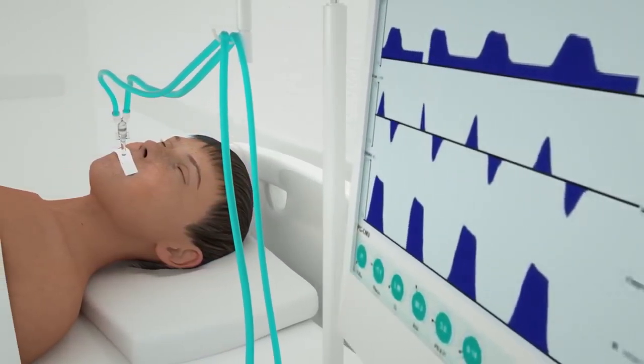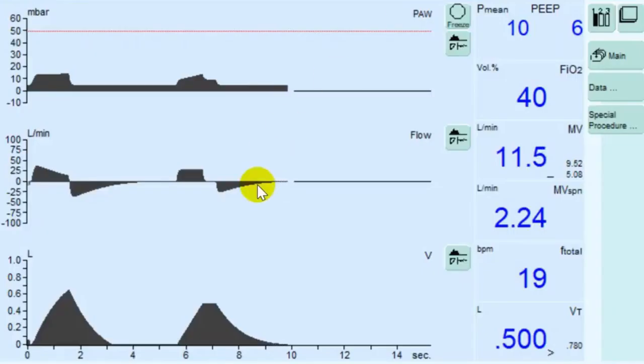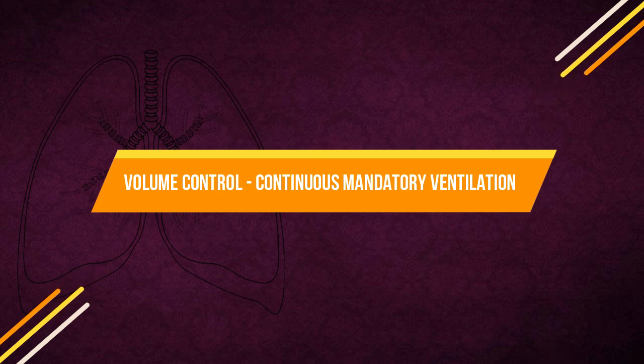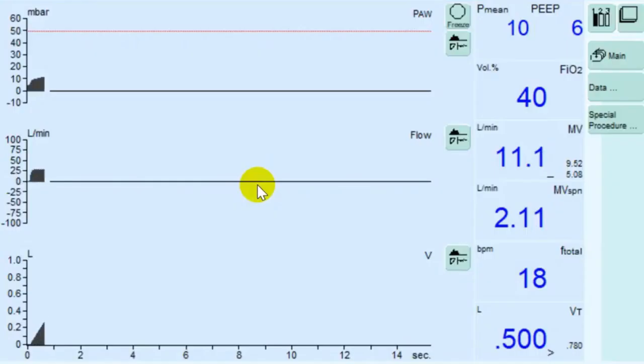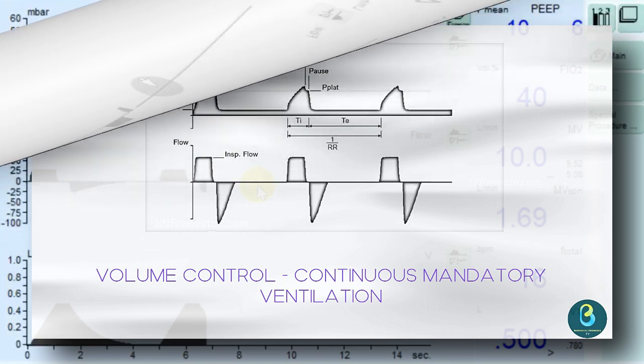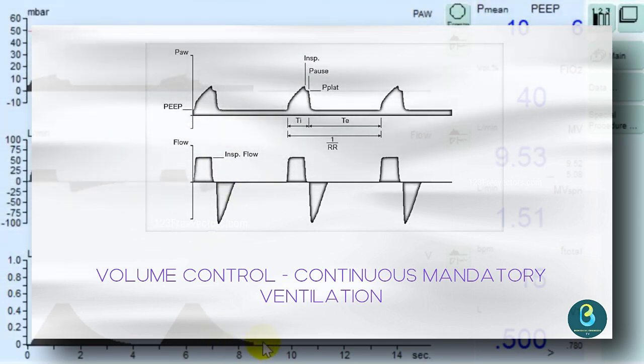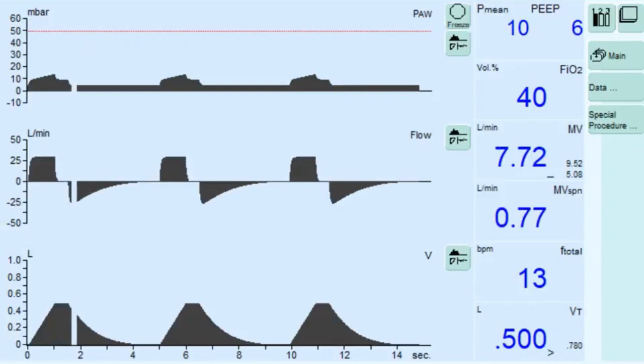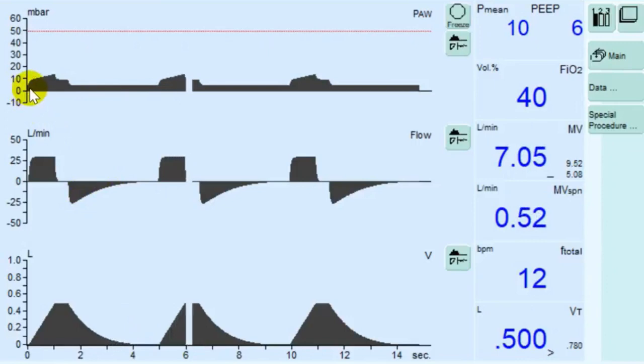Let's begin with Volume Controlled Ventilation Modes, starting with Volume Control Continuous Mandatory Ventilation. In this mode, the patient receives the set tidal volume with every mandatory breath. The applied breathing volume is independent of changes in the lung mechanics. The number of mandatory breaths is defined by the frequency, meaning the minute volume remains constant over time.